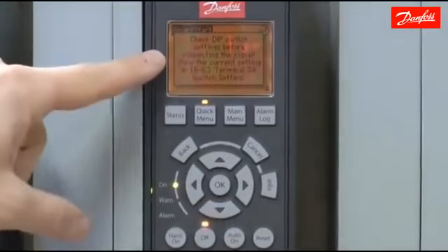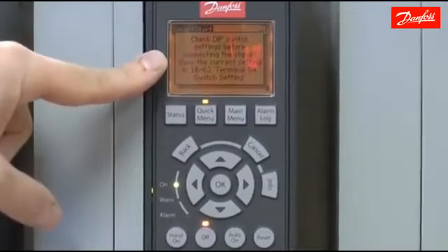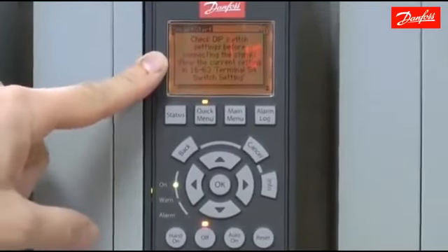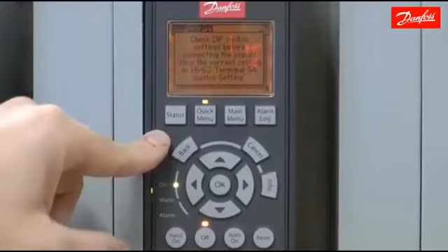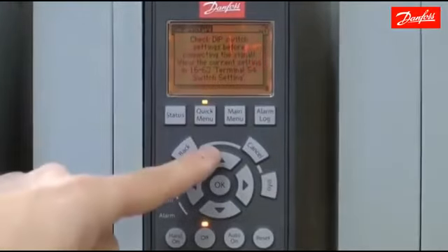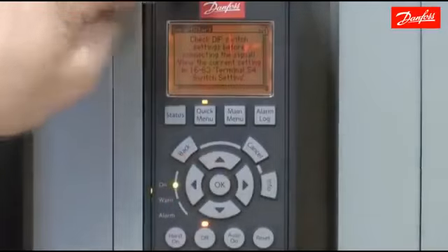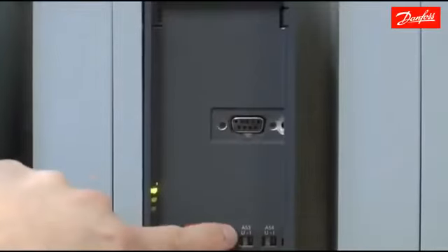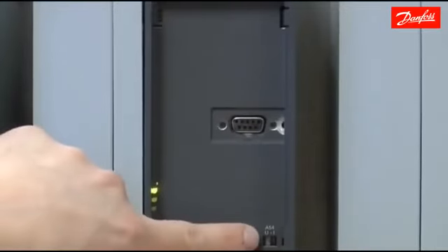It's warning me to check the dip switch settings before connecting the feedback signal. There's a dip switch behind the LCP for both analog inputs, one for 53 and one for 54. They default in the voltage position, which is to the left for each switch. This switch is for 53, this is for 54.